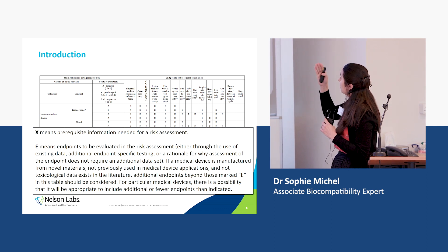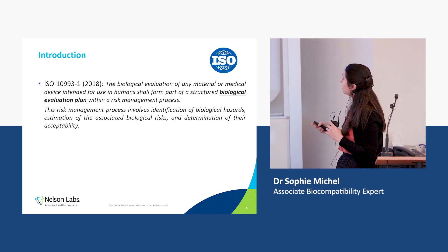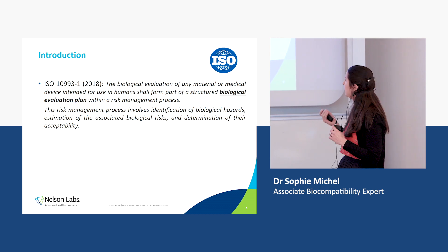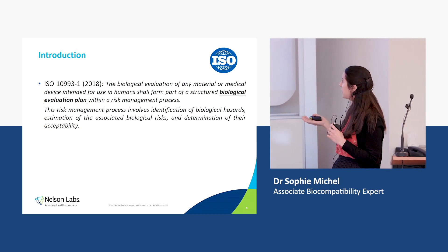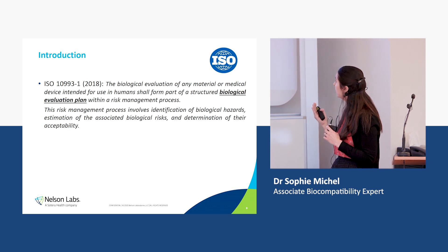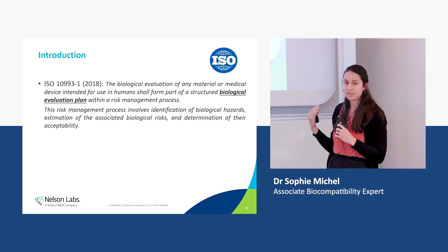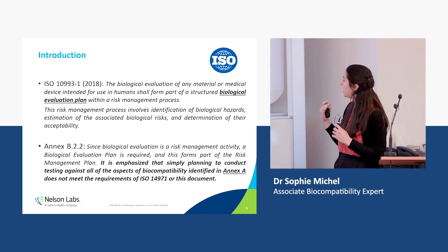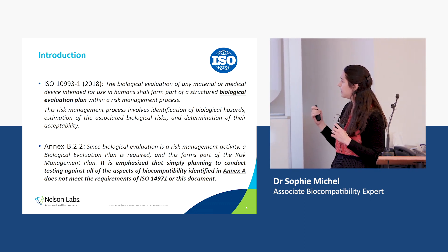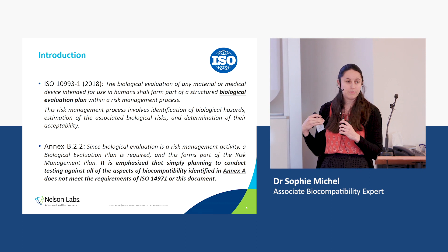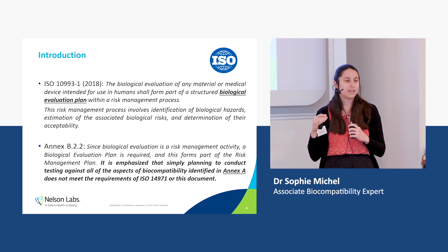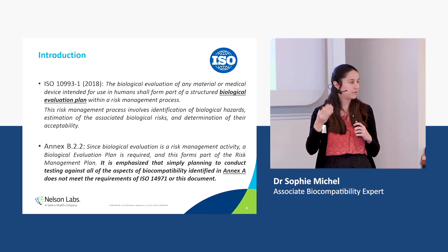So what is a biological evaluation plan in this framework? This is defined by ISO 10993-1. The risk management process or BEP involves identification of biological hazards, estimation of the associated biological risk, and determination of their acceptability. Annex B.2.2 also says that simply planning to conduct testing against all aspects of biocompatibility identified in Annex A does not meet the requirements of ISO 14971 or this document — so you cannot use the checkbox approach like we used to do in the past.